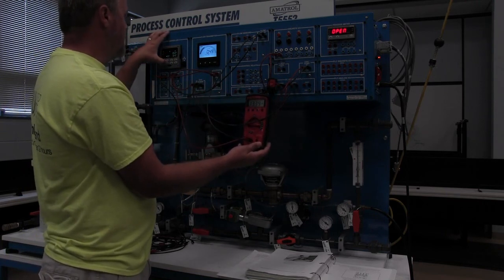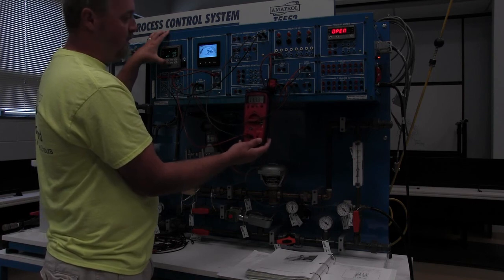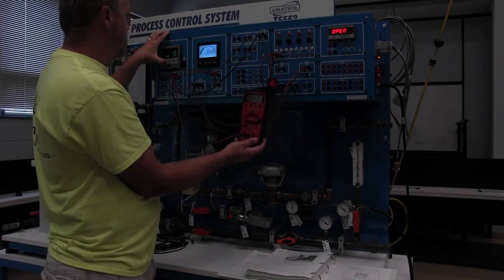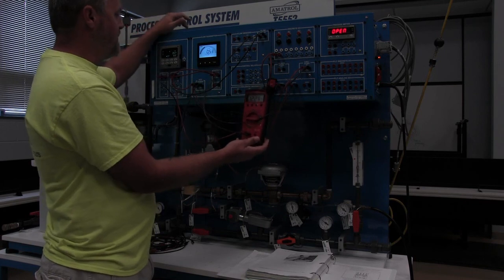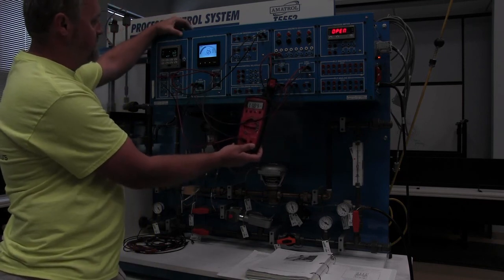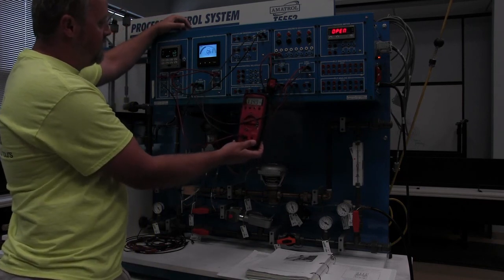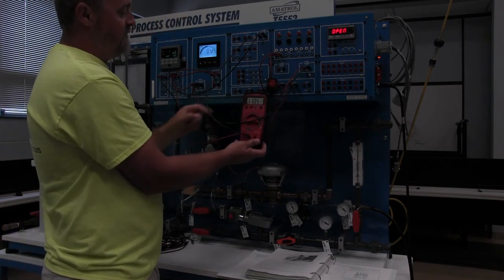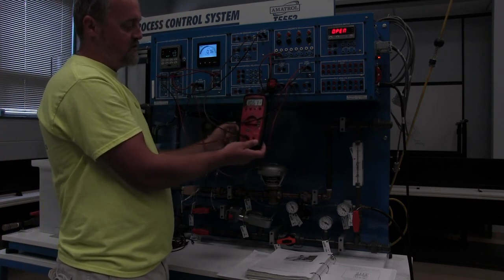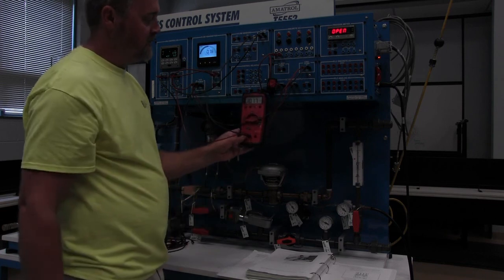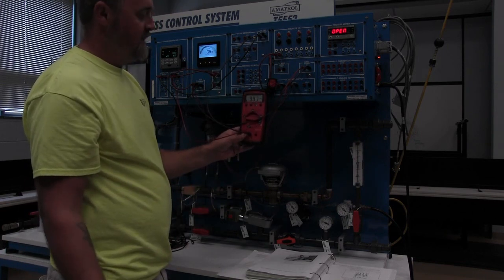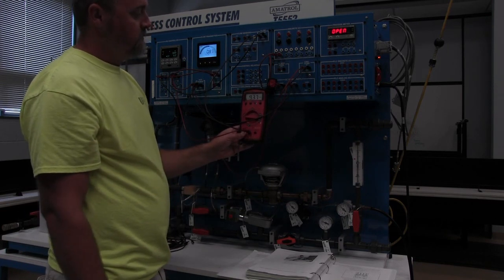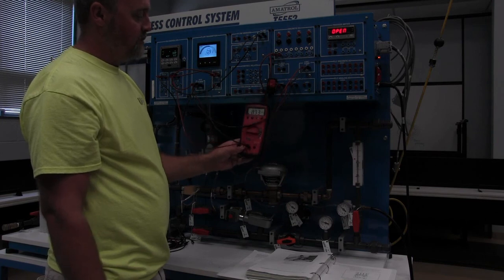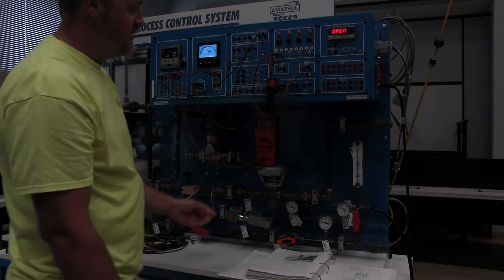I'll take this set point and I'm going to go all the way up to it. Looks like 1.5 is the highest I can go for the set points we put in the controller. In order to get to that 1.5, this valve needs to open, so we need to drop this milliamp signal, which it is. It's down to a 10, a 9.5, a 9. So proportionally, everything is working like it should.